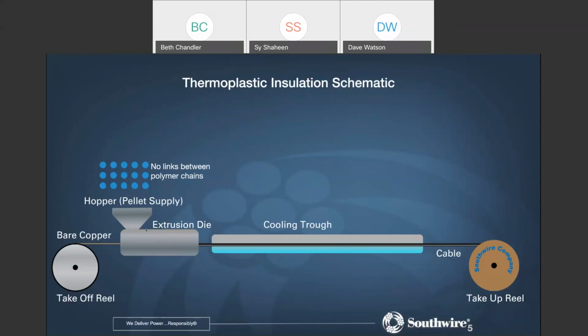So we have these combinations of materials put into the extrusion die. The insulation material, and perhaps jacket material as well, is extruded over the bare copper, and then it runs through a cooling trough. Now, this step is what's going to differentiate between the thermoplastic products and the thermoset products. The cooling trough is simply a water tray that the product is pulled through to cool down, and then we wind it up on a take-up reel. So in the output of this product, there are no links established between the polymer chains. These polymer chains are melted, extruded, and formed over the bare copper, but there's no further linking occurring between the polymer chains as it goes through the cooling trough.